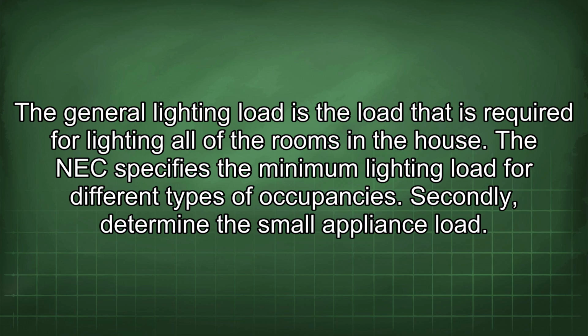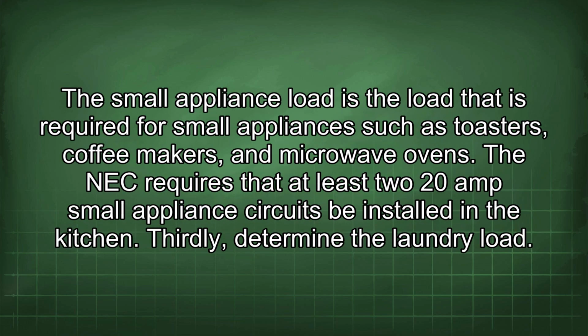Secondly, determine the small appliance load. The small appliance load is the load that is required for small appliances such as toasters, coffee makers, and microwave ovens. The NEC requires that at least two 20-amp small appliance circuits be installed in the kitchen.